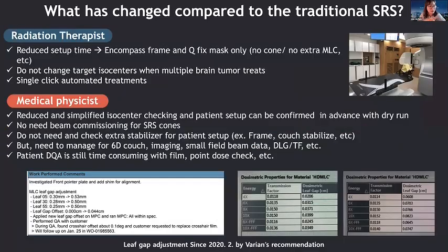For radiation therapists, they can also reduce the setup time, because they can only use the Encompass frame and the Q-fix mask, and they don't really need to attach an additional cone and so on. The MLCs, they don't need at all. And they don't need to change the target isocenters when multiple targets are treated at a time. Also, once they click the button, everything in the treatment will go through automatically, so they don't really need to think about every button, every step. So it's very convenient.